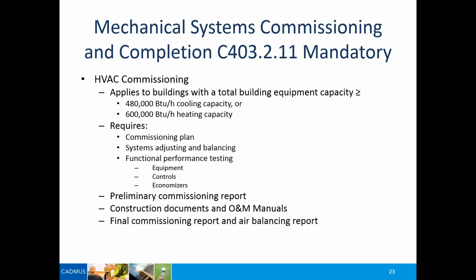We've sealed our duct systems up. We've put insulation on the distribution systems. So the bulk of our savings right now are really going to be in controls, to make sure that the systems are operated properly to match the loads. And so we need to make sure those controls are operating correctly. So the code will require you to submit a commissioning plan with the initial submittal of the project to the building department. There are no real requirements on format. If you're already doing commissioning and have something that works, it essentially says, here is how I am planning on commissioning the mechanical system.